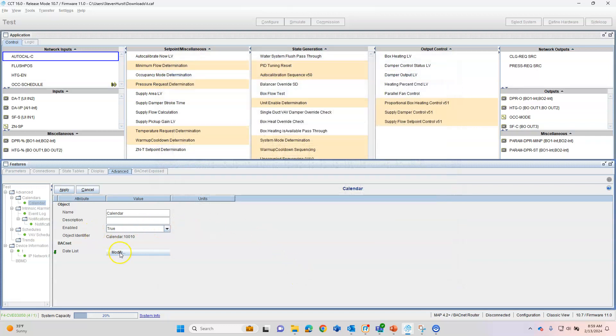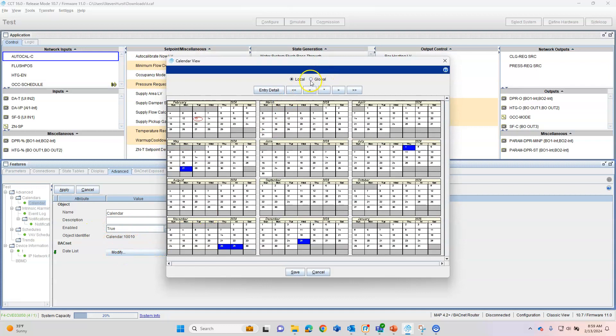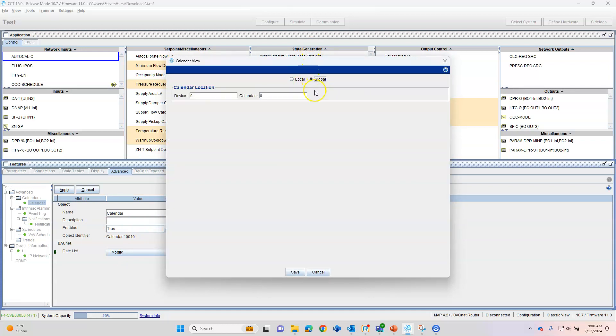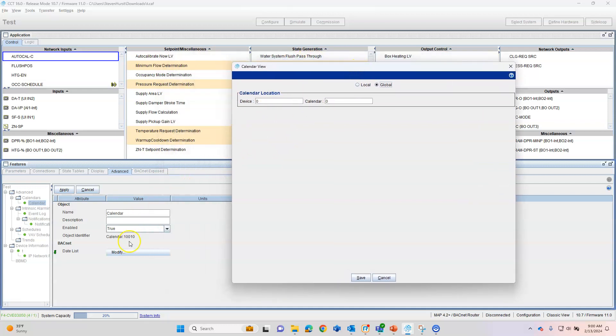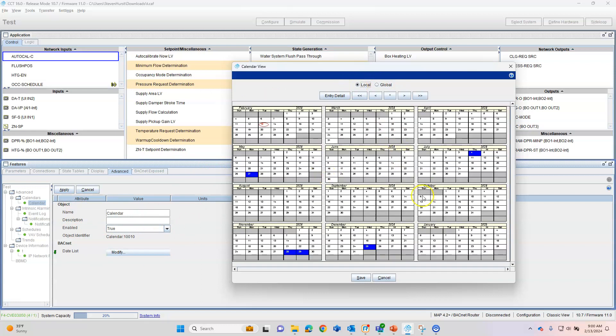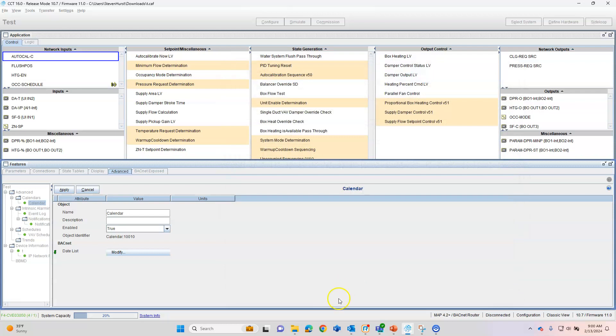We can also have a global calendar. So we can do one calendar on one controller in the building. As long as they're all linked together on one BACnet system, we can do the device ID of the device and then the calendar ID, which would be, you know, this guy right here is 10010. We can reference all the controllers to this calendar right here just by going in and adding a calendar and looking at the global and just filling out one local one. So that's a nice feature there. So we'll leave those dates in there and we'll hit Save.